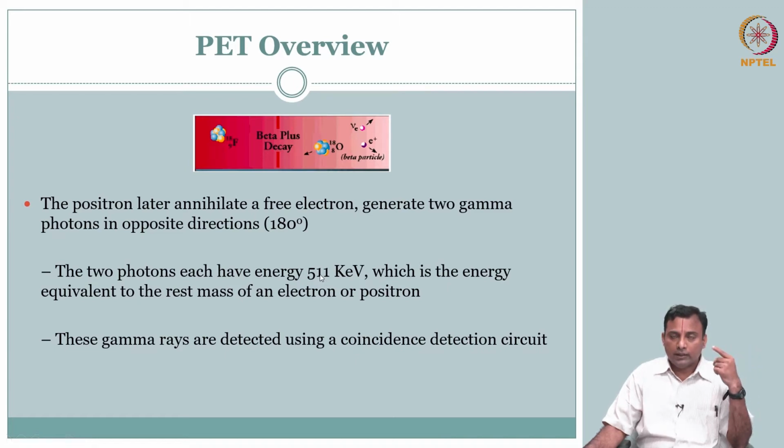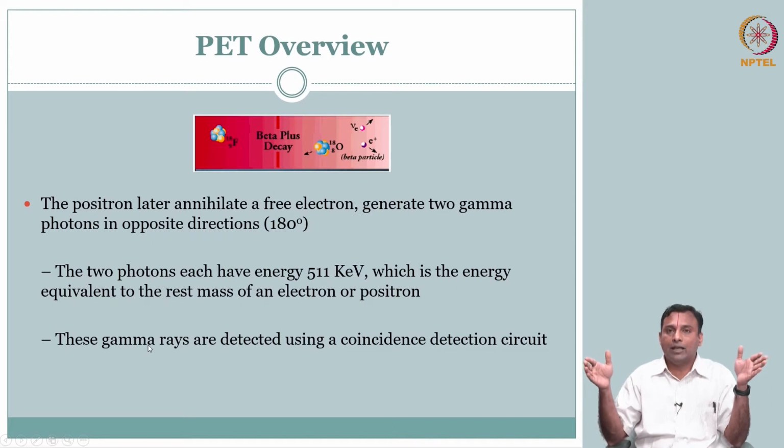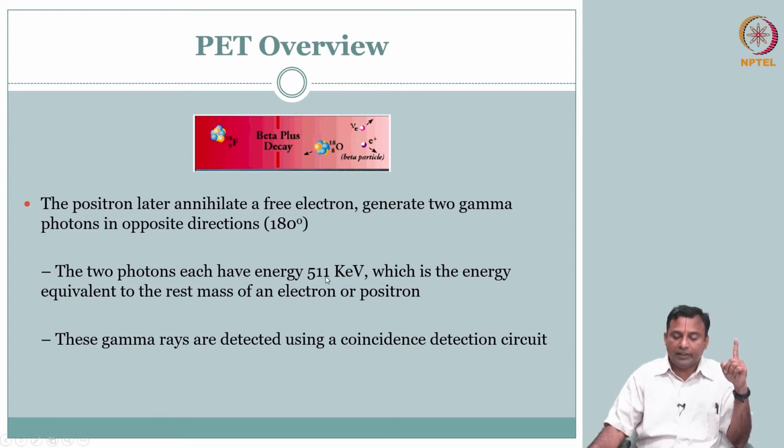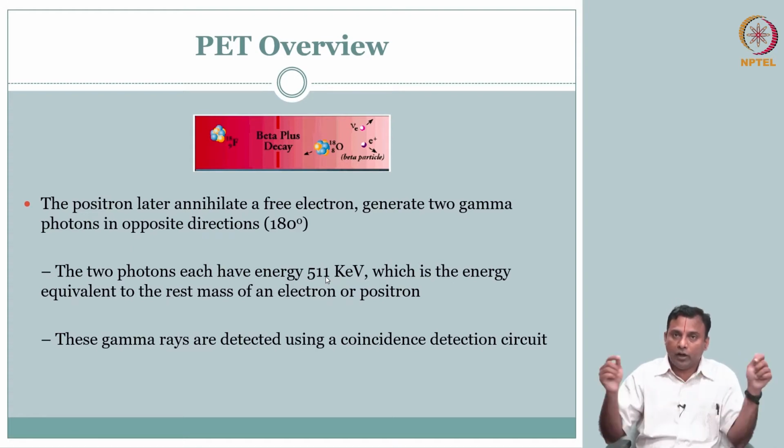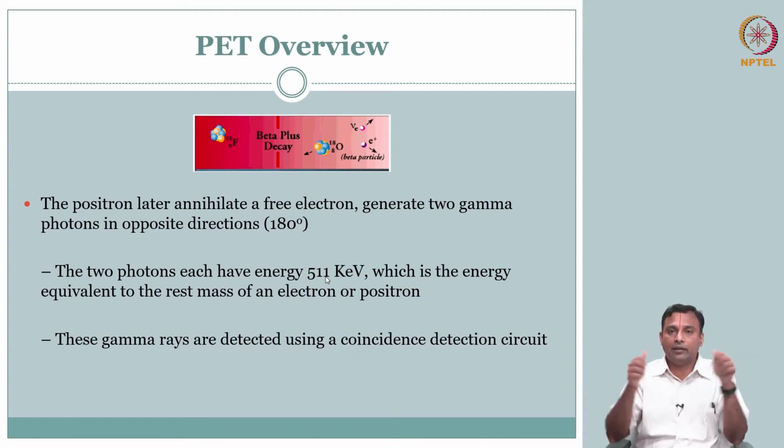So the important detail in positron emission tomography is here also you are ending up detecting only the gamma photons. However, it has a specific energy, which is 511 keV, and more importantly, if one decay happens, you are going to record two photons at 511 keV that are exactly in line, exactly 180 degrees in direction, and that is a key information.